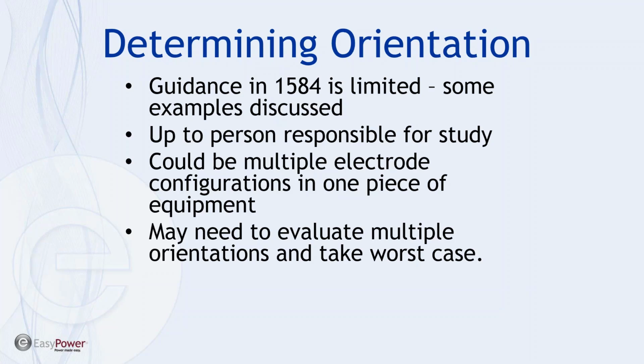Some examples are discussed, and I just covered some of those pictures. So it's up to the person responsible for the study to detail the assumptions that have been made. And what I recommend is, as we talked about earlier, taking pictures. If you have a calibrated eyeball and you've determined that the bucket or the enclosure that you're looking at or the electrode configuration is non-standard, it may be beneficial to have a wooden yardstick or some other element you can put in the frame as you take the reference measurement, as you take the digital image. So again, the intent is to try to minimize multiple trips to the site and collect data as much as possible and record it specifically in digital images.